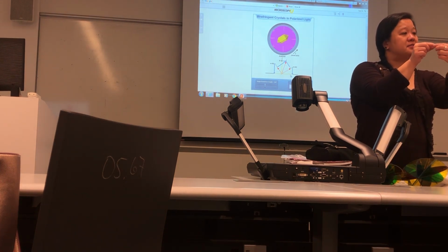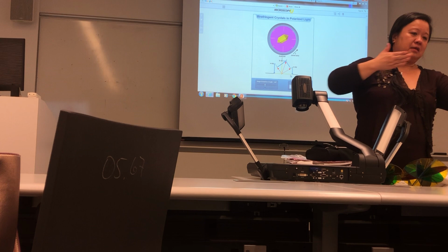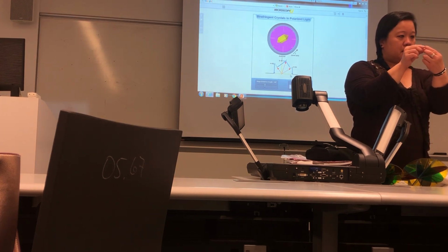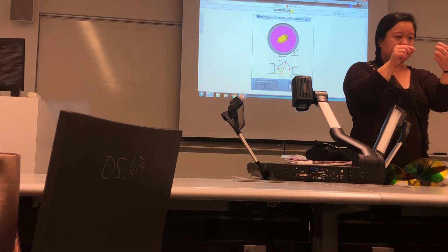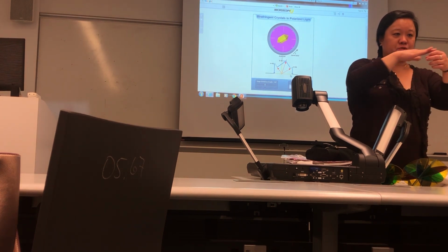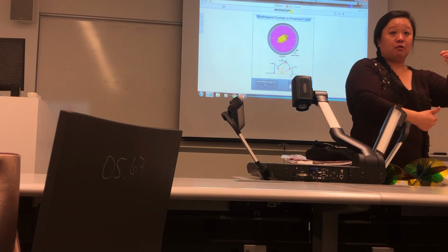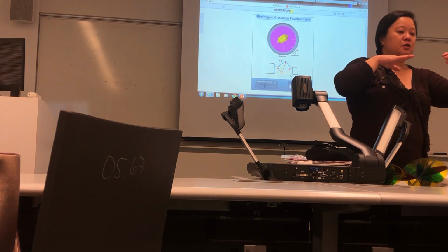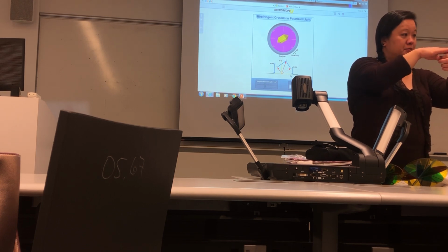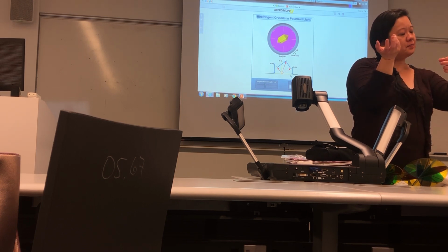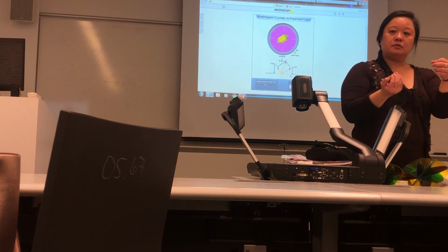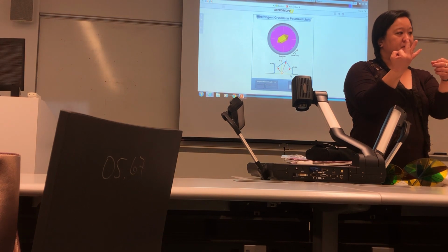And there's also that little slot, which is at an angle, and there's normally a blank black piece inserted into that with a hole in it, and the hole is supposed to be positioned so that the light can go through the hole, okay? Basically, you put your blank in there to prevent dust from getting into your microscope. When you're ready to measure optical properties of your samples, you can take out the blank, and in those kits, you've got 3 compensators.